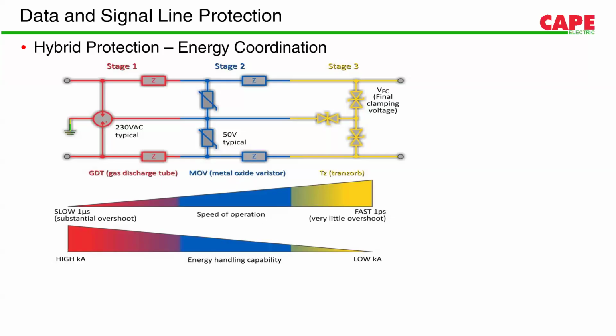Below you see the graph of the energy handling capacity. The GDT has the highest, the MOV somewhat lesser, and the diode very little. Whereas for response time, diodes have very fast response time, the MOV is somewhat slower, and the GDT is slowest compared to the diode. In general, in the power circuit also, the acceptable response time is up to 100 nanoseconds. You can find SPDs with various response times from 1 to 100 nanoseconds. 1 is the best quality. The Tranzorb series SPDs have a response time of 1 nanosecond. 25 is good quality, and 100 nanoseconds is also an acceptable result.